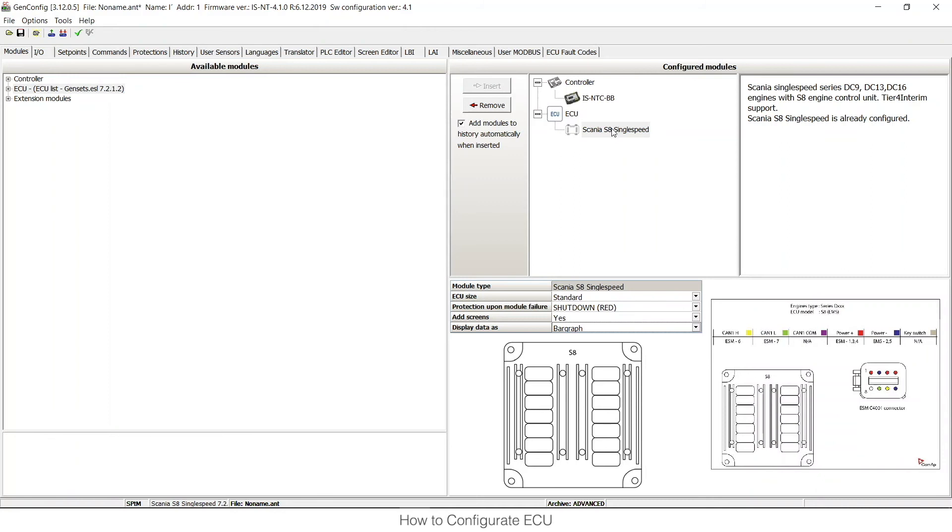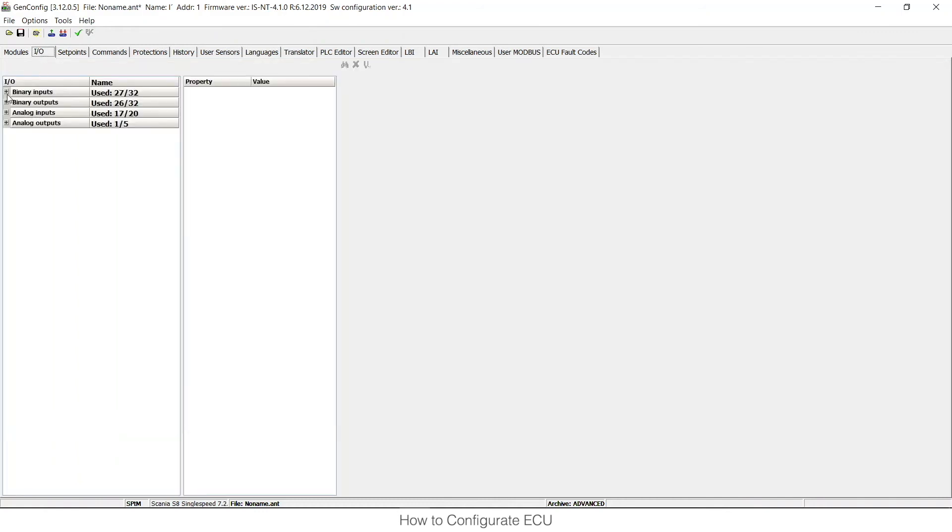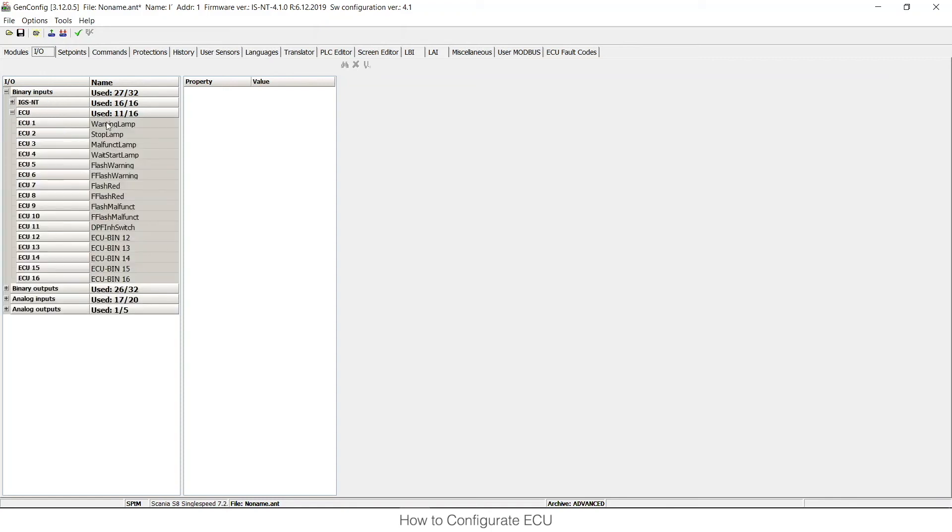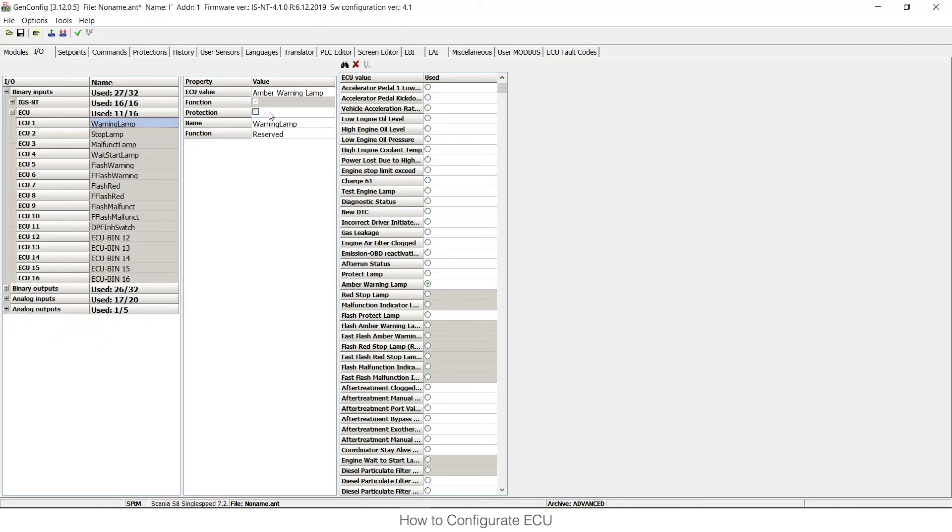So this is just the configuration of ECU to have it in the IntelliSys NTC-BB but I can also go to inputs and outputs and I can check all the inputs and outputs in the ECU group here as I would do it for standard physical inputs and outputs. So here I can choose what ECU value is used and I can process it in the way that we are used to with standard inputs and outputs to connect functions and protections and so on.